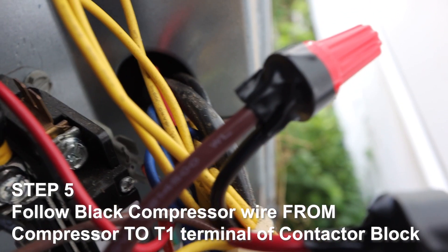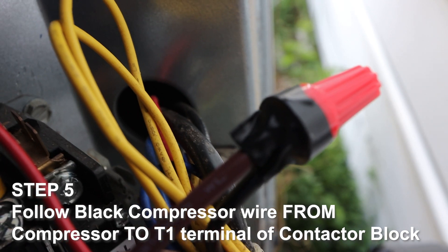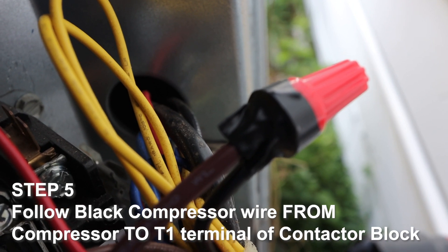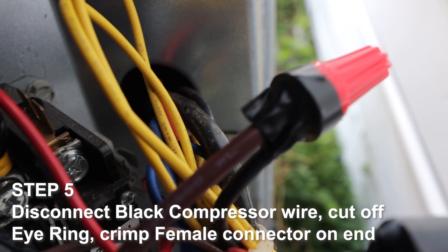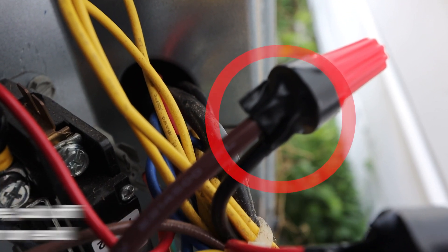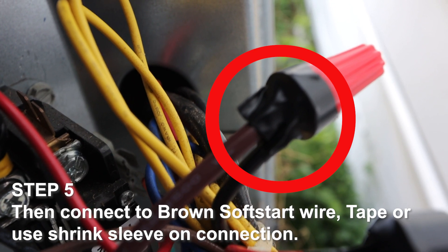Step 5. Follow the black compressor wire from the compressor to the T1 terminal on the contactor block. Disconnect the black compressor wire. Cut off the eye ring, crimp a female connector on the end, and connect it to the brown soft start wire. Tape the connection.